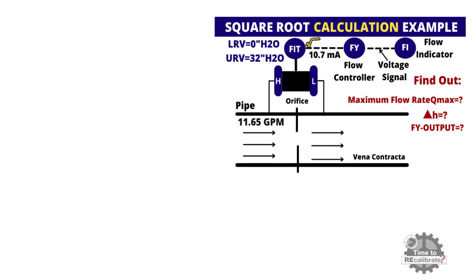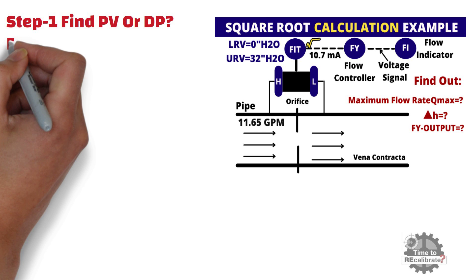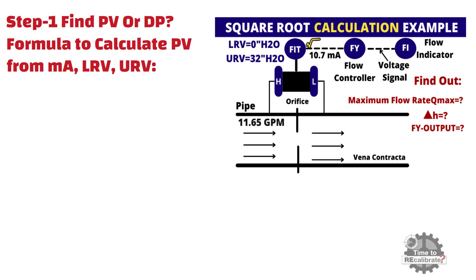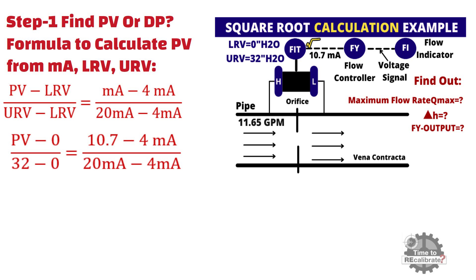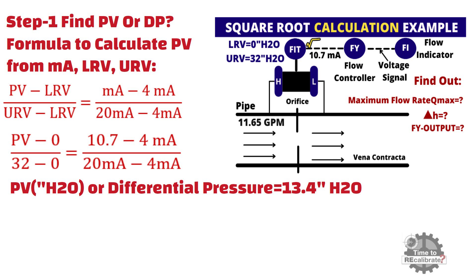Step number 1: Find the process value or differential pressure value. To find the process value, we have a standard formula to calculate it from milliampere, lower range value, and upper range value. Put the milliampere value, lower range value, and upper range value into this equation and do the simple math. You will get 13.4 inch H2O as the differential pressure value.